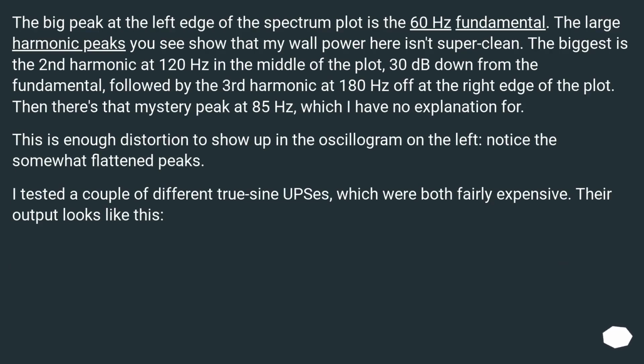The big peak at the left edge of the spectrum plot is the 60 Hz fundamental. The large harmonic peaks you see show that my wall power here isn't super clean. The biggest is the second harmonic at 120 Hz in the middle of the plot, 30 dB down from the fundamental, followed by the third harmonic at 180 Hz off at the right edge of the plot. Then there's that mystery peak at 85 Hz, which I have no explanation for.